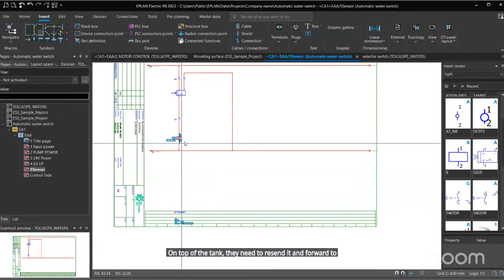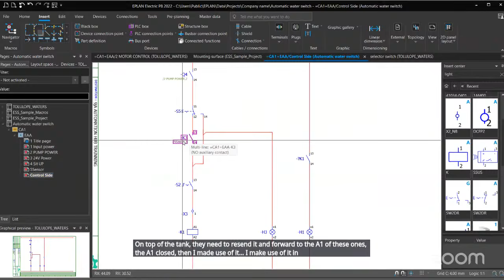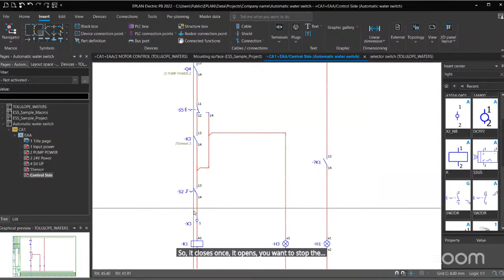So the ultrasonic sensor will be placed on top of the tank, then it will send 24 volts to the A1 of this relay. Once the A1 closes, I make use of it in the control side as K3 here. So it closes, once it opens, the motor stops, the pumping stops. This is K1 for the pumping machine, the pump. Once it's closed or open, either way, it just stops it.